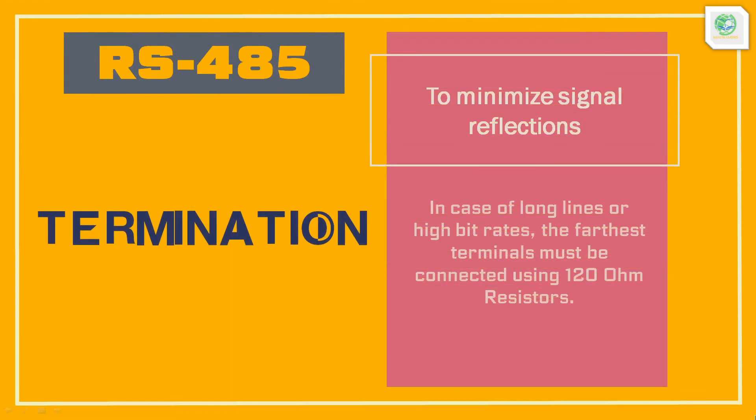In case of high bit rates or long lines, the two farthest terminals must be connected using 120 ohm resistors. This is done to minimize signal reflections as much as possible.